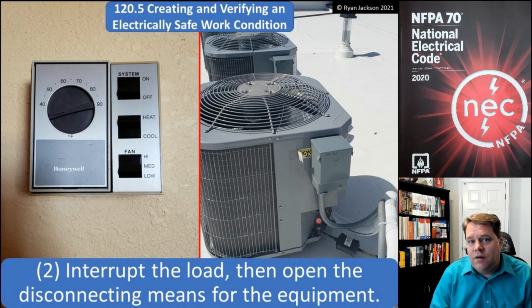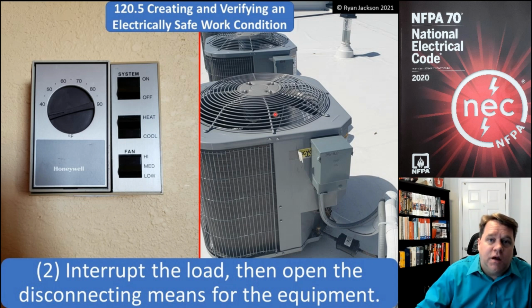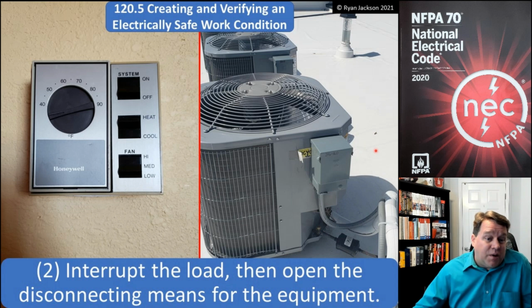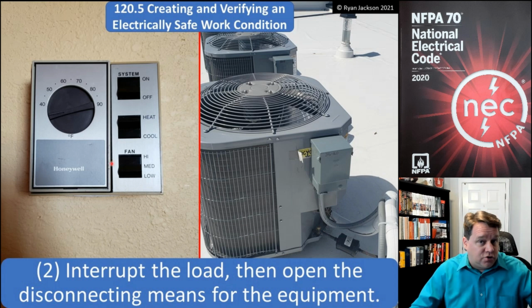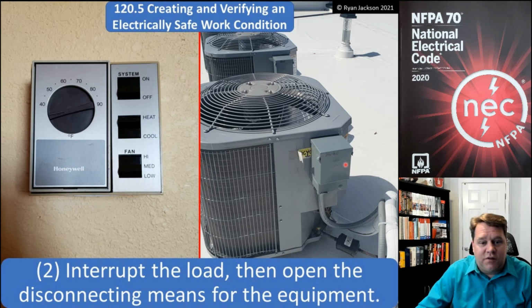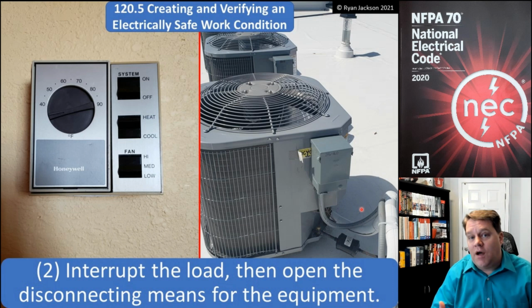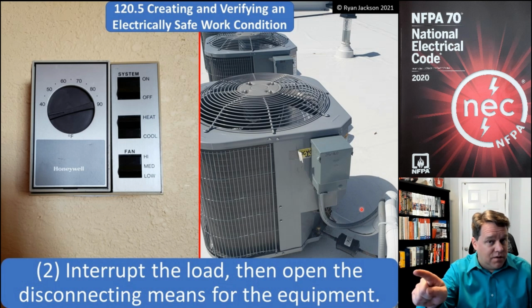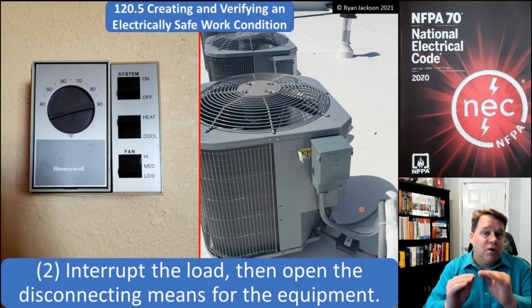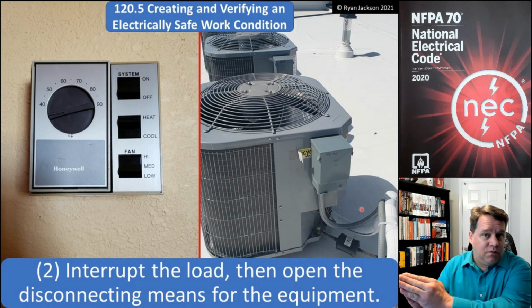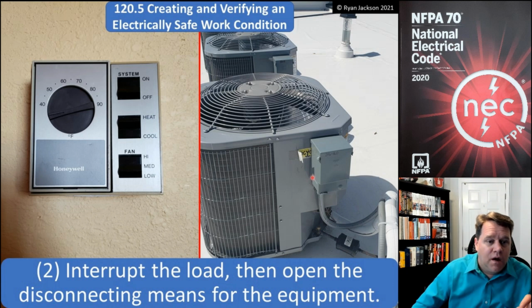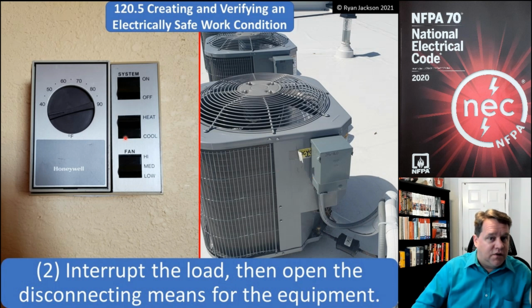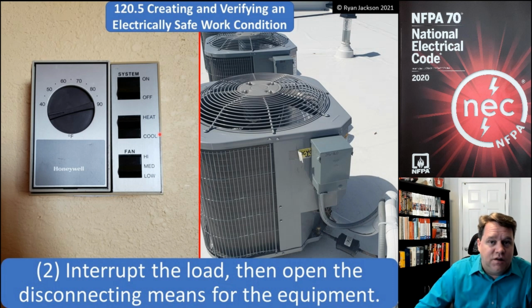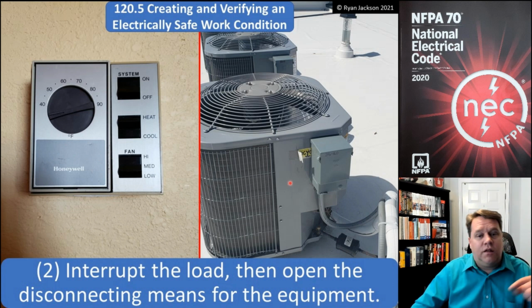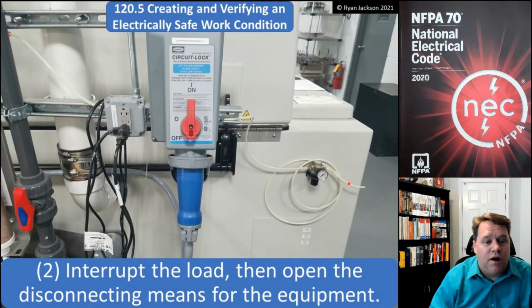You're a lot less likely to have something bad happen if the motor's not spinning when you shut it off on the power circuit. So if it's possible, let's interrupt the load first with a control circuit and then shut off the power circuit. And we're going through item 1 right now in the hierarchy, which is eliminating the hazard, but we're not finished with item 1 yet. Right now, we're reducing the hazard as we go, and that's the second list in the priorities. So we're going to work on something in the safest way possible until we get it completely de-energized and we've removed the risk. So let's start by shutting off the motor with the control circuit if possible, and then we'll go through and disconnect the load.